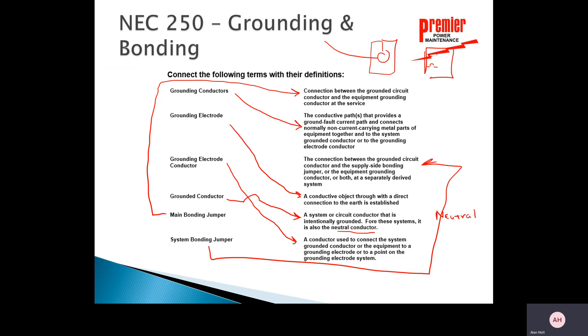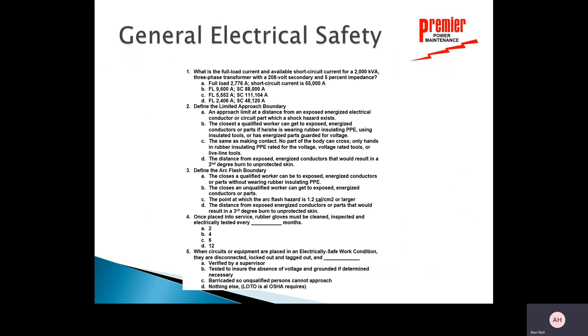Now for some general electrical safety questions. The first question asks: what is the full load current and available short circuit current for a 2000 kVA three-phase transformer with a 208-volt secondary and five percent impedance? Notice I didn't give the high-side voltage because it's not needed — I'm dealing with the low-side voltage. The equation we need is for full load current I_FL.